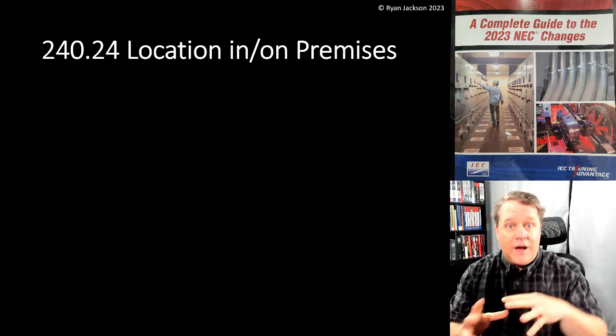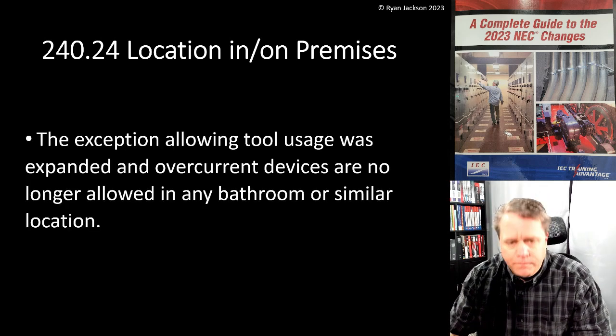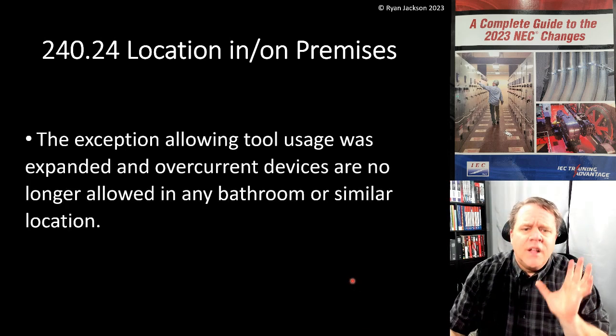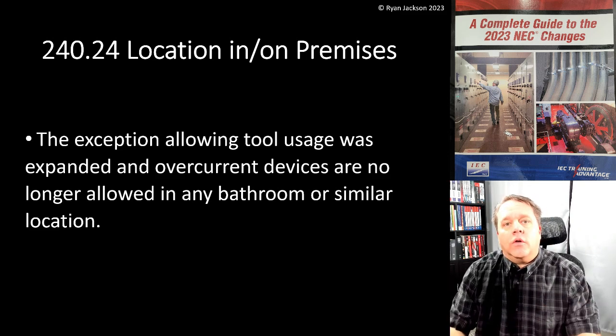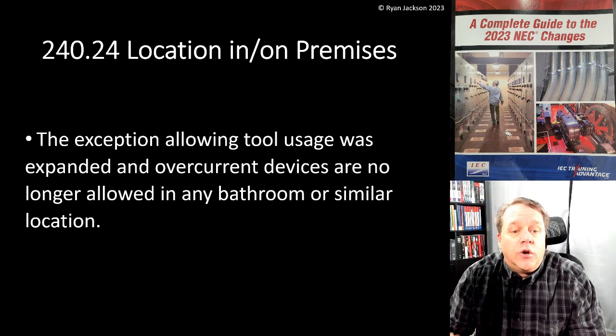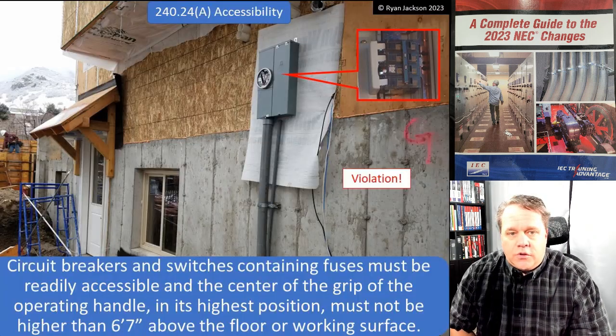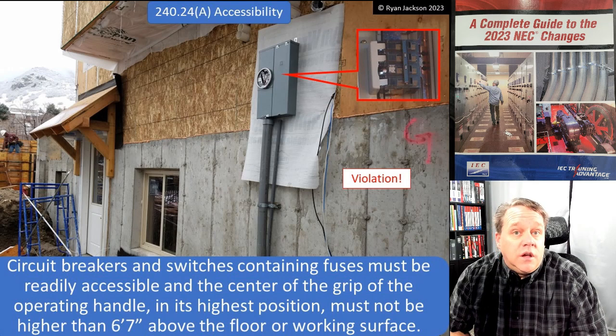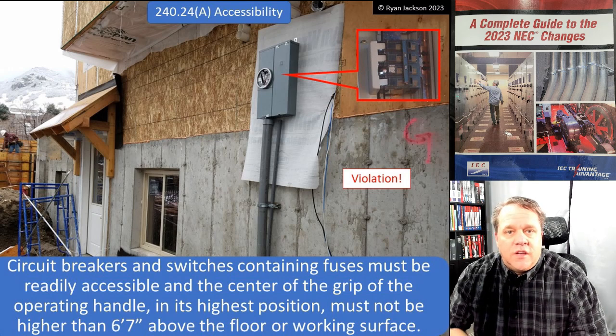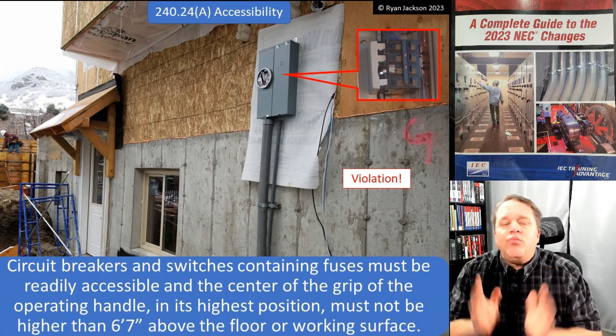So outside, inside, above six foot seven, down low — that's what 240.24 covers. The exception allowing tool usage was expanded, and overcurrent devices are no longer allowed in any bathroom or similar location. Under 240.24(A), accessibility: circuit breakers and switches that contain fuses must be readily accessible.